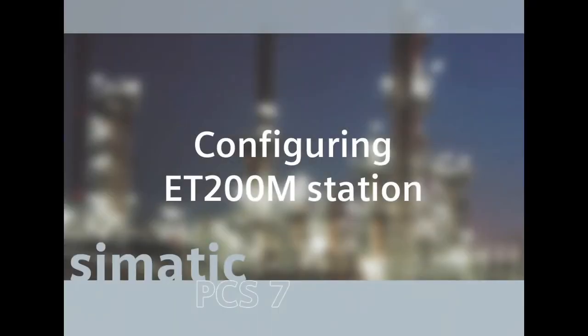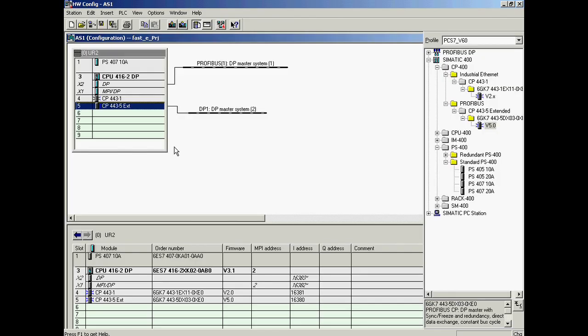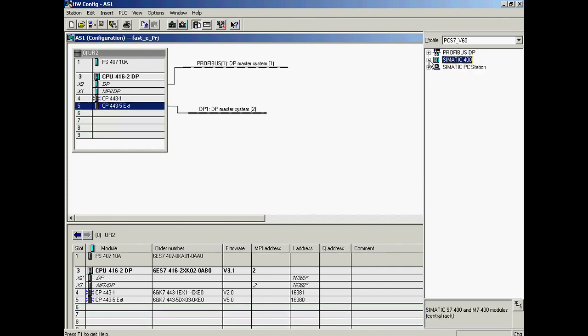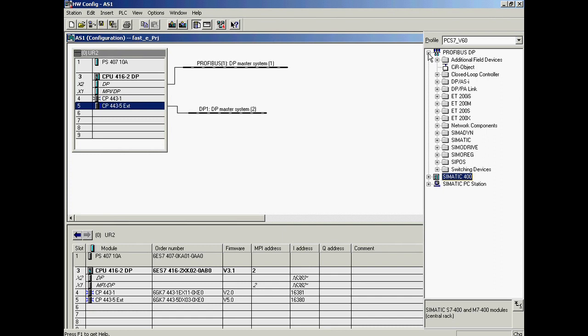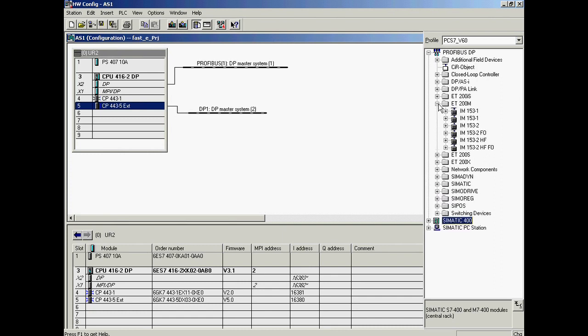The S7-416 automation system hardware is now fully configured and has been assigned to the system bus network. An ET200M distributed I/O system with an address of 3 is connected to the Profibus DP segment called DP1. It will be configured in the next step, starting with adding the IM 153-2 to the Profibus string DP1.